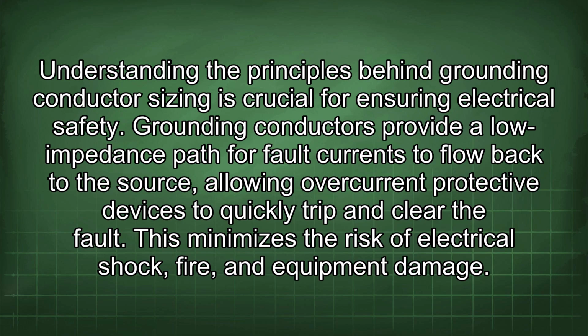Understanding the principles behind grounding conductor sizing is crucial for ensuring electrical safety. Grounding conductors provide a low impedance path for fault currents to flow back to the source, allowing overcurrent protective devices to quickly trip and clear the fault. This minimizes the risk of electrical shock, fire, and equipment damage.